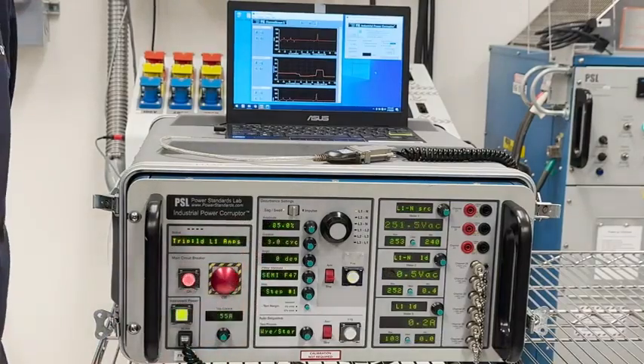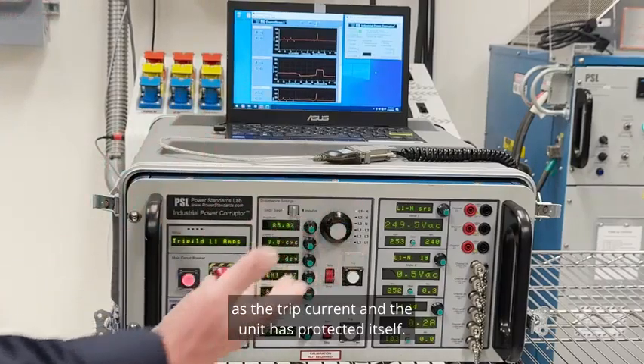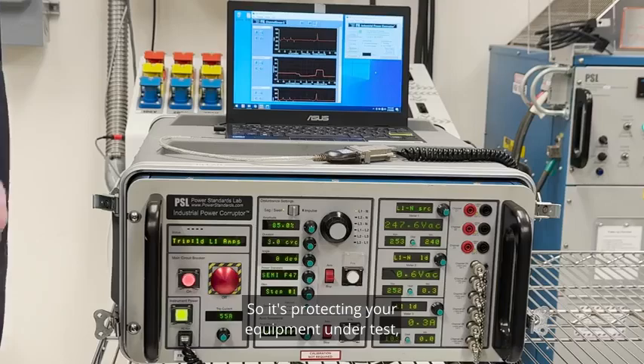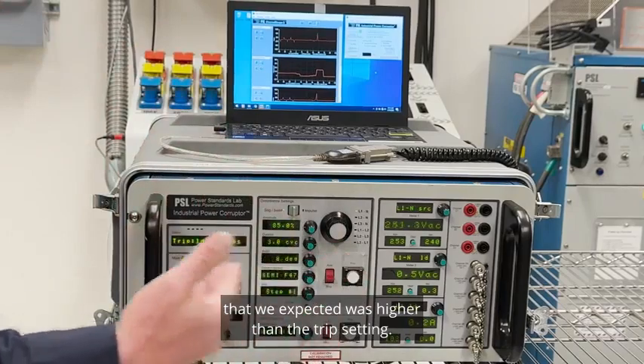The inrush has exceeded what we have as the trip current and the unit has protected itself. So it's protecting your equipment under test, but clearly the current that we expected was higher than the trip setting.